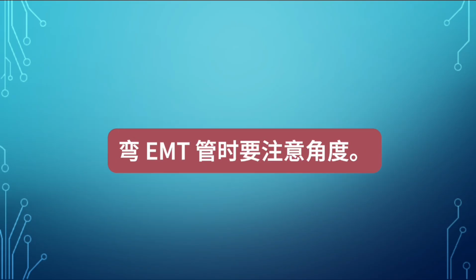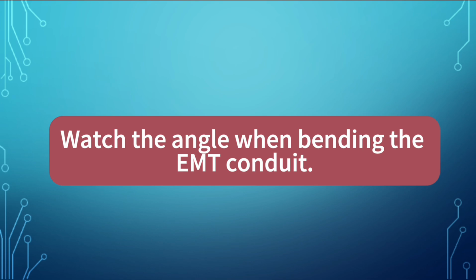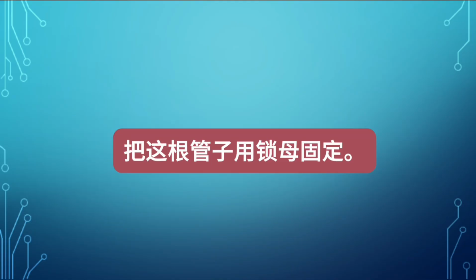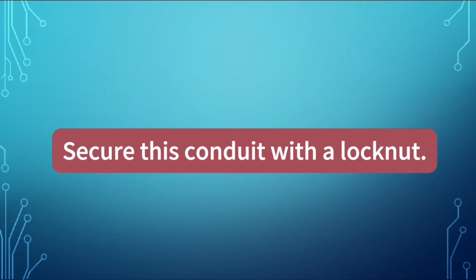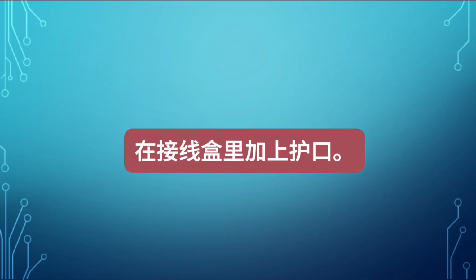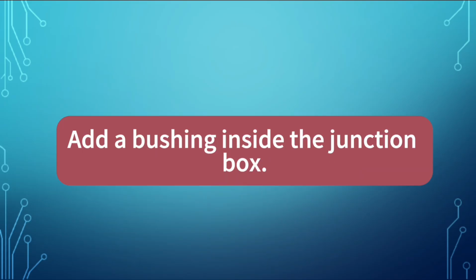Watch the angle when bending the EMT conduit. Secure this conduit with a lock nut. Add a bushing inside the junction box.